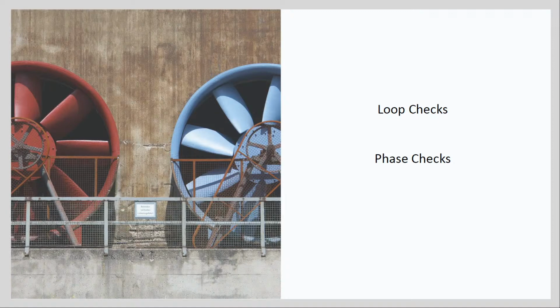So this is a bit of a higher level overview of protection relay testing, but it can be quite involved and there's quite a bit required to do protection relay testing. I see in some cases that owners or the commissioning team may require that the supplier or vendor of the equipment do relay protection settings, but I also know in some of the past projects I've been on, the owner has the capabilities to do their own protection relay testing, and it's definitely a skill to be learned to know all the details of relay protection testing. But I can point you to a really good resource.